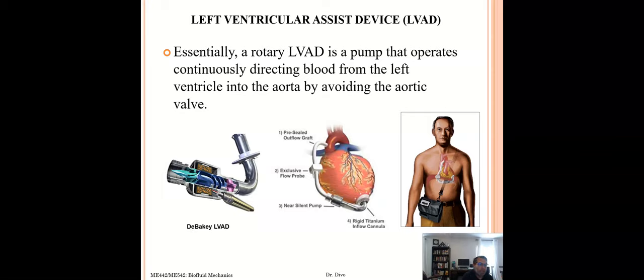And therefore, they can live for years or decades. These devices opened the door for these types of therapy to become bridge to recovery or destination therapy. Bridge to recovery essentially means: implant this device, and maybe the heart will recover at some point with some additional therapy, and if it does, then remove it. And destination therapy basically means: okay, implant this device.